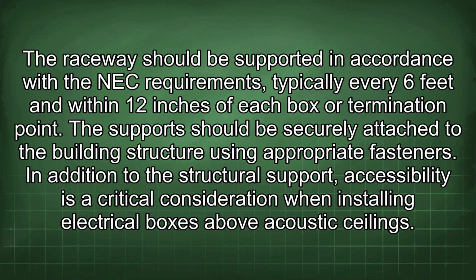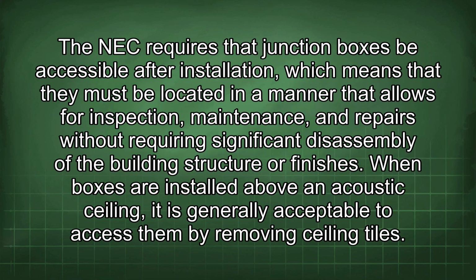The raceway should be supported in accordance with NEC requirements, typically every 6 feet and within 12 inches of each box or termination point. The support should be securely attached to the building structure using appropriate fasteners. In addition to the structural support, accessibility is a critical consideration when installing electrical boxes above acoustic ceilings. The NEC requires that junction boxes be accessible after installation, which means that they must be located in a manner that allows for inspection, maintenance, and repairs without requiring significant disassembly of the building structure or finishes.